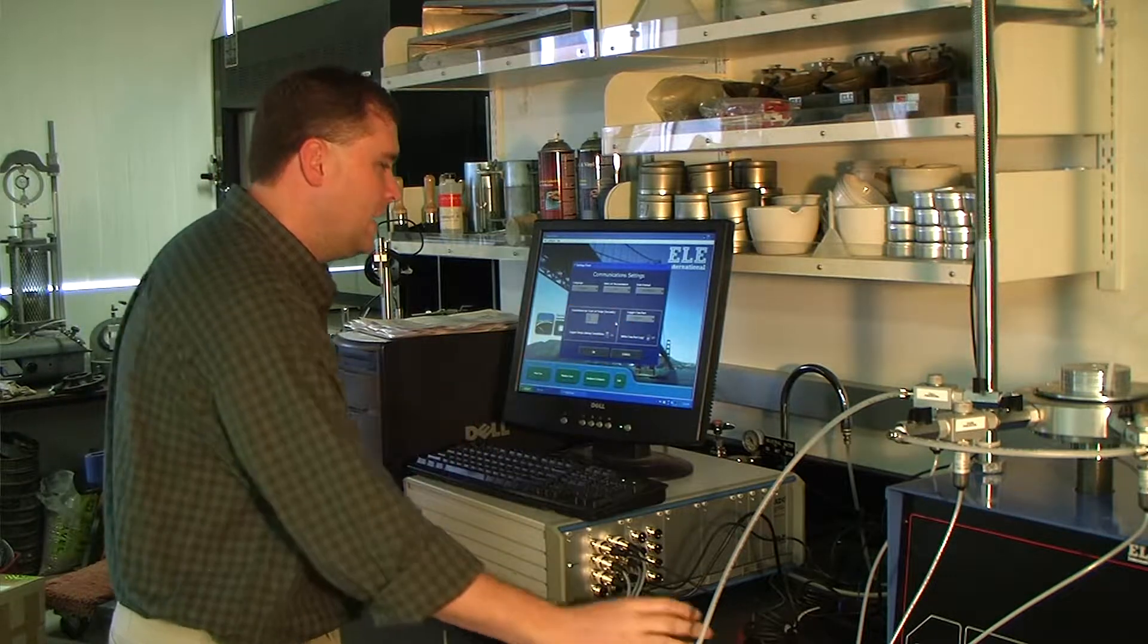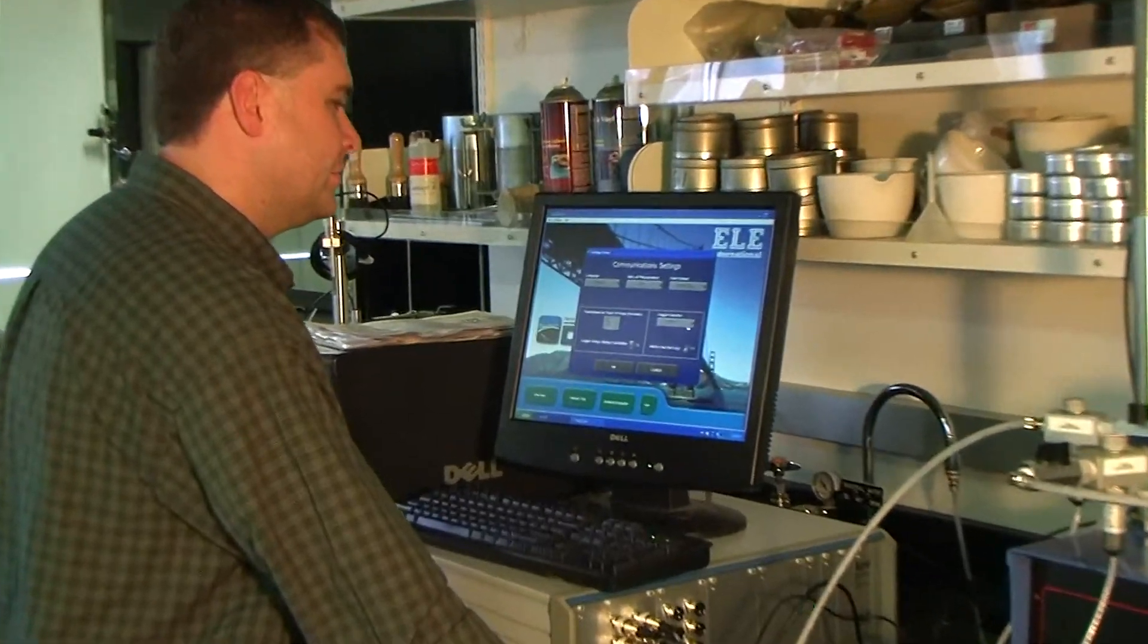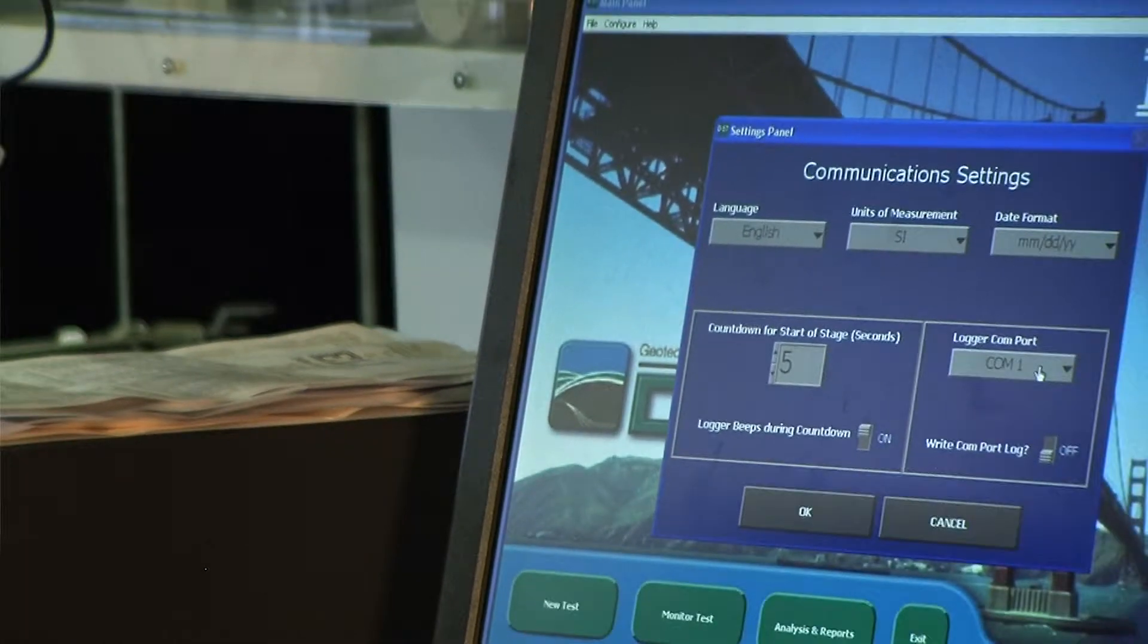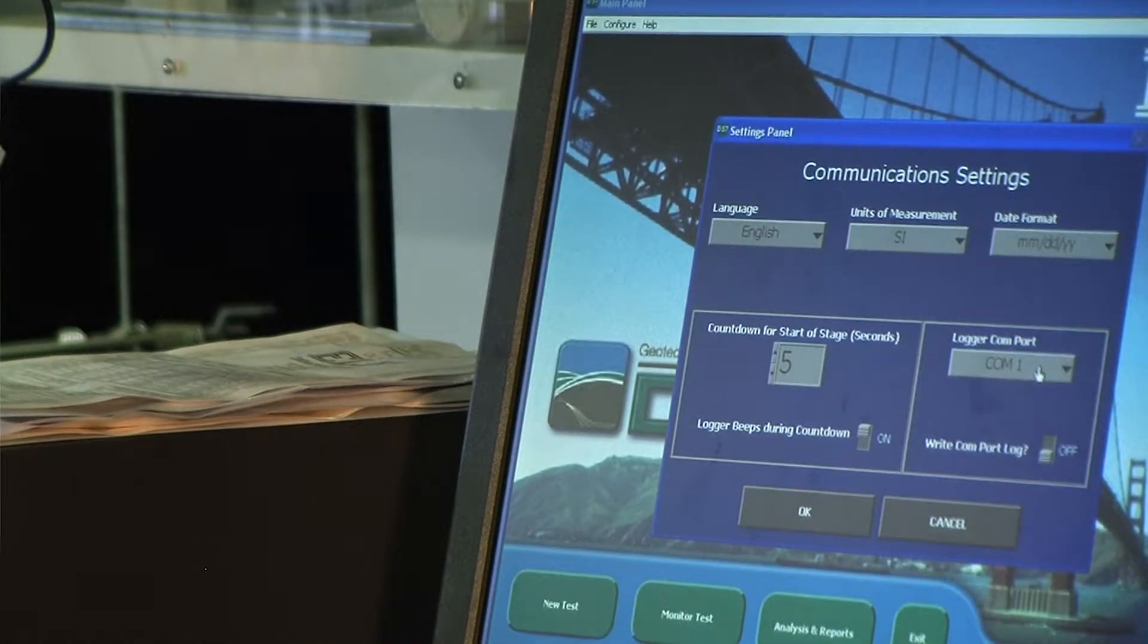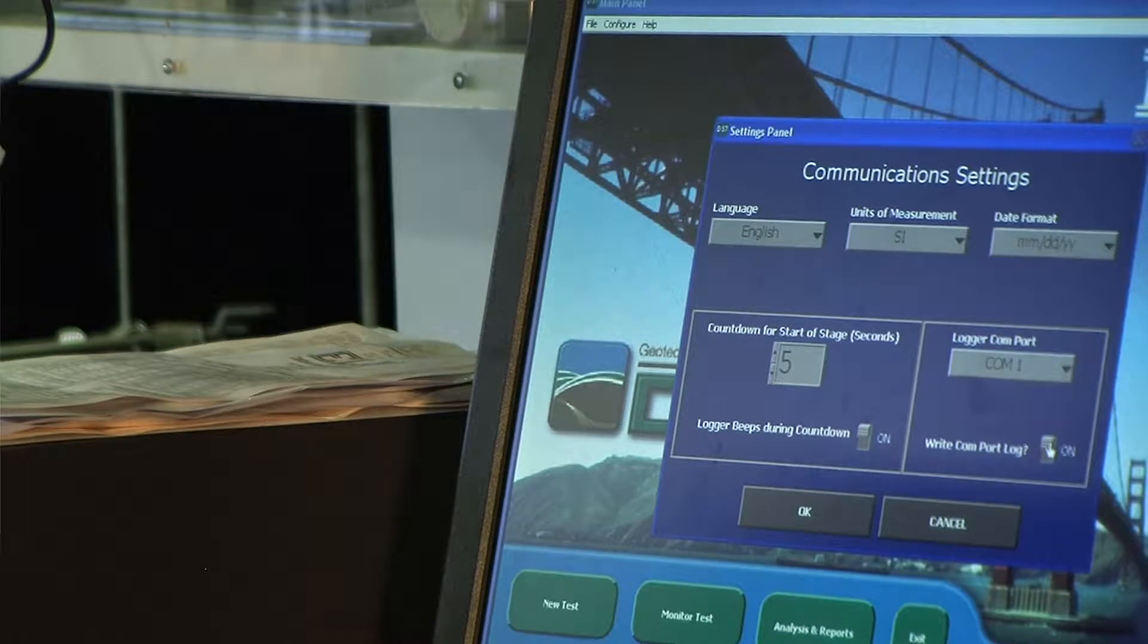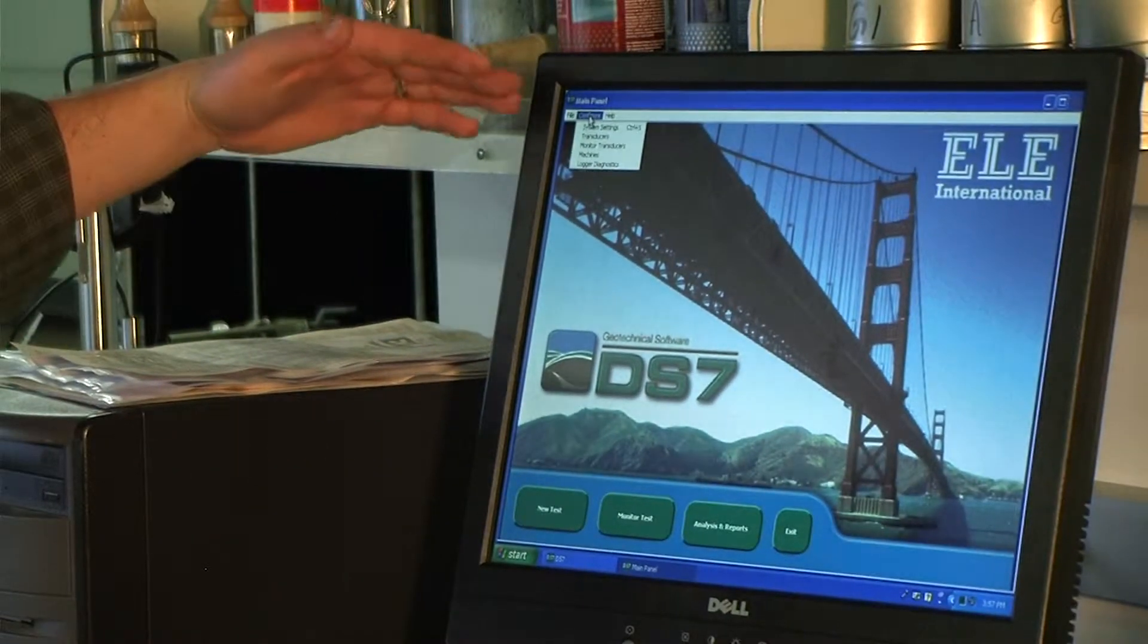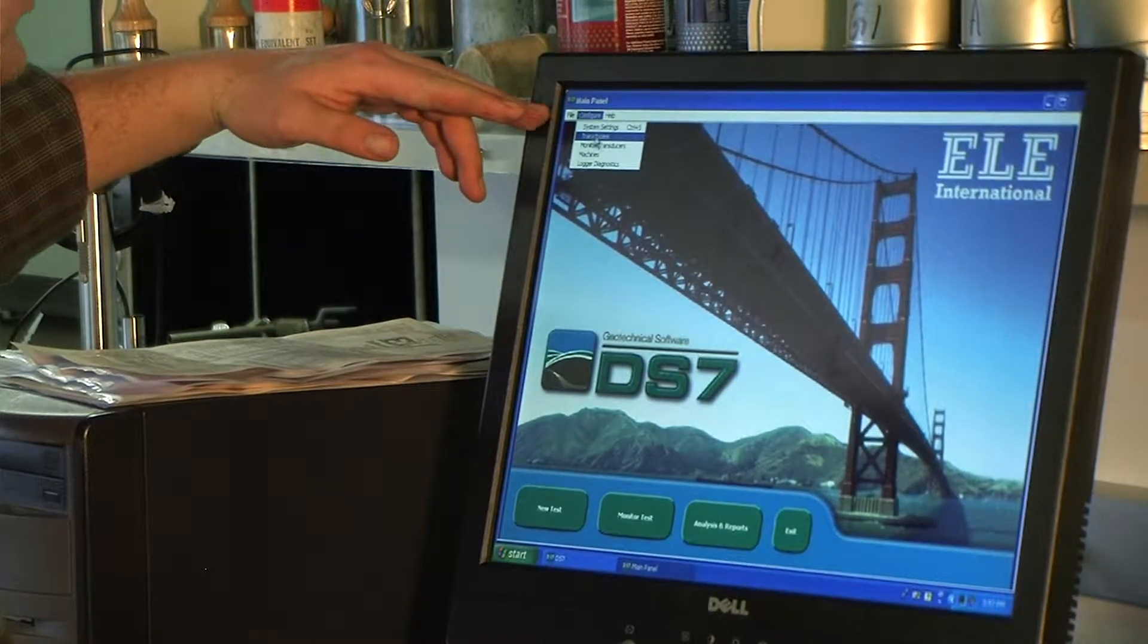The one on the right here is if you have communication errors or communication issues, you can change which port on the computer that the ADU is connected into. You can also write a log for the communication port between the ADU and the software itself. That's used for troubleshooting if necessary. So I'll click OK. We'll just keep it as is. Go back to configure. That was system settings. The next one we'll look at is transducers.